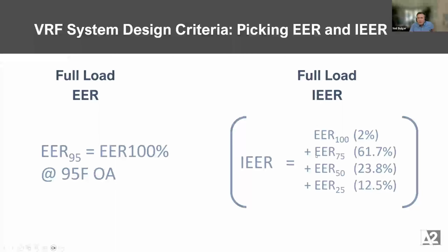It's really made up of a test where they have to say at different capacities, how efficient is it? And then it weights those and says, well, we know these systems are mostly going to run at about 60% capacity, or 60% of the time they'll be at that. But from a modeler, you might get a very high EER sticker value. And in some ways, it doesn't really help you model that system.